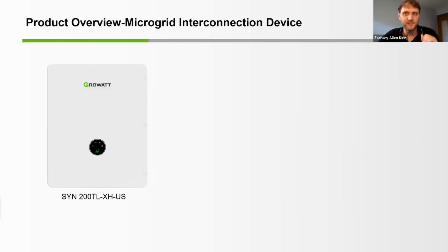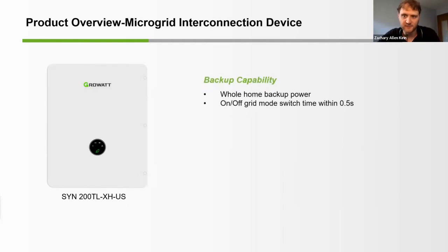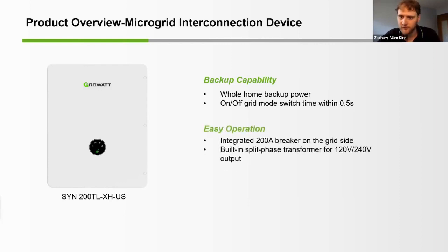However, we also have this device. It is the SYN. It is our solution for whole home backup and interfaces with the V3 model of the MIN inverter. The V3 model does not feature the secondary load backup. It only features the grid output, making things a little bit more simple for the customer. The SYN is a microgrid interconnection device to support the whole home backup and continue to operate the inverter during grid outages. The product has a less than 500 millisecond switchover time.